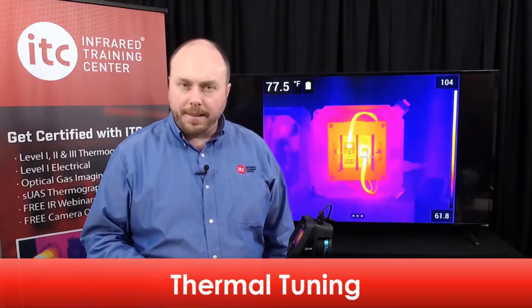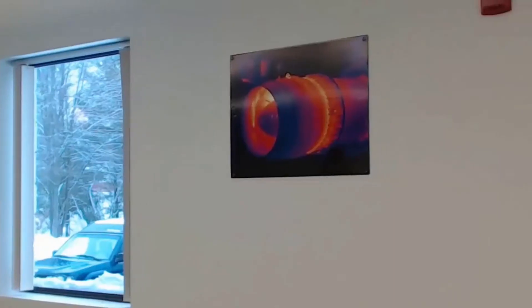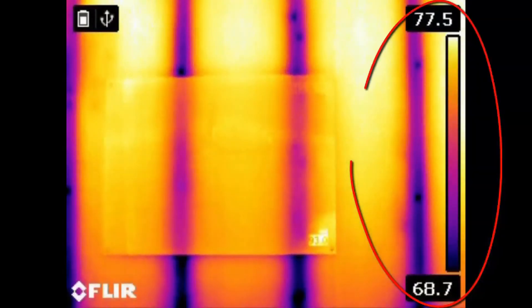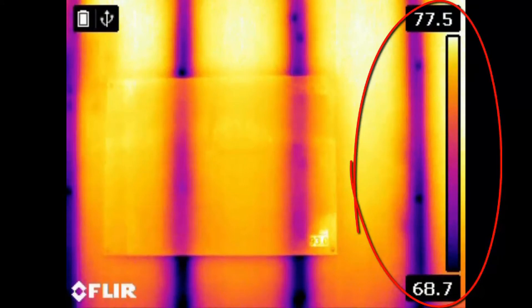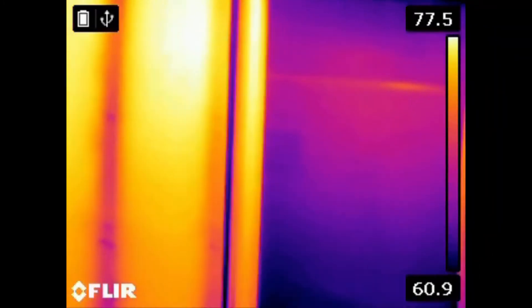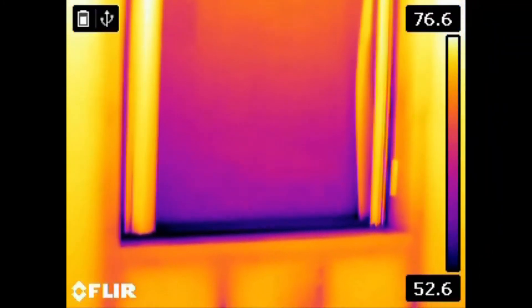Thermal tuning is the process of changing the size of the temperature scale in the camera — what's known as adjusting span and level in our certification classes. Adjusting this scale modifies the brightness and contrast of your thermal image, allowing you to highlight important areas of thermal detail. By default, the camera is set to Automatic Adjustment Mode, which automatically sets the scale based on the hottest and coldest objects in the frame. However, manual adjustment may be required, especially if there are extraneously hot or cold objects within the field of view.